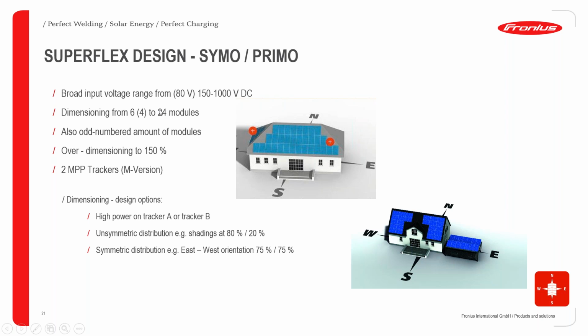For this, we have a wide range of input voltage, 80 to 1000 or 150 to 1000 for the Primos and Symos respectively. For dimensioning, we can have from 6 up to 24 modules per string, 4 in the case of small inverters, as earlier described. And of course, odd numbers of modules are possible because of its flexibility. So you're not restrained to a particular order of installation of modules, which is an added advantage. And again, we can over dimension our inverters up to 150%.